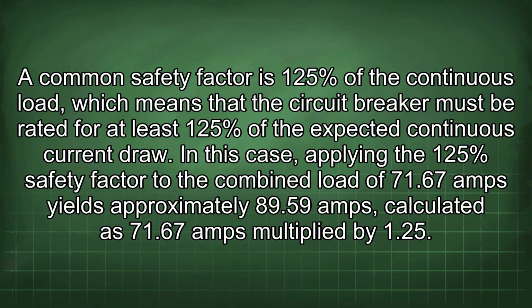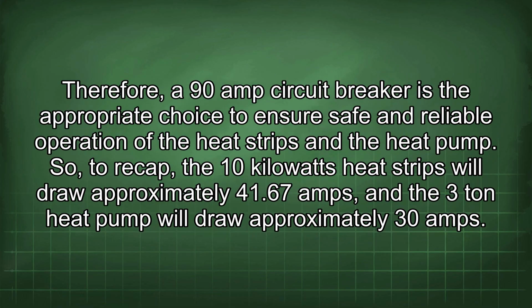A common safety factor is 125% of the continuous load, which means that the circuit breaker must be rated for at least 125% of the expected continuous current draw. In this case, applying the 125% safety factor to the combined load of 71.67 amps yields approximately 89.59 amps, calculated as 71.67 amps multiplied by 1.25. Therefore, a 90 amp circuit breaker is the appropriate choice to ensure safe and reliable operation of the heat strips and the heat pump.